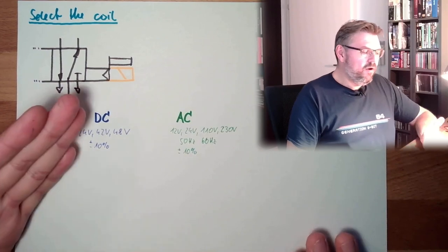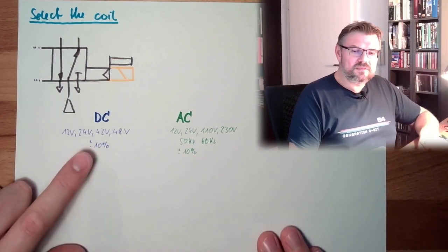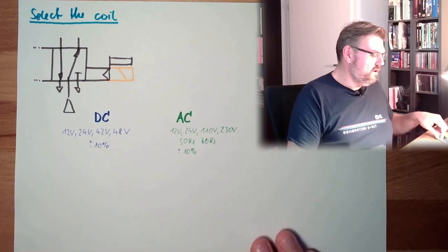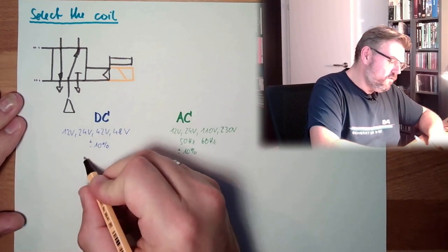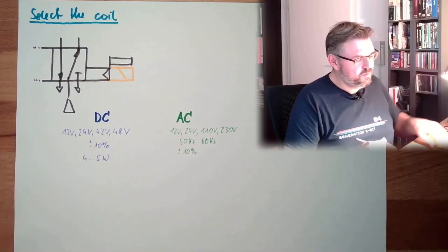How much power do we drain? These DC coils, they usually use somewhere around 4 to 5 watts. This is the typical power.